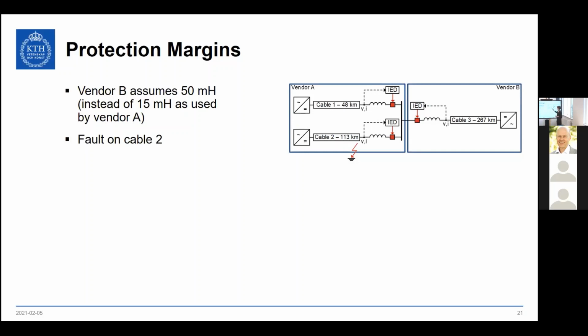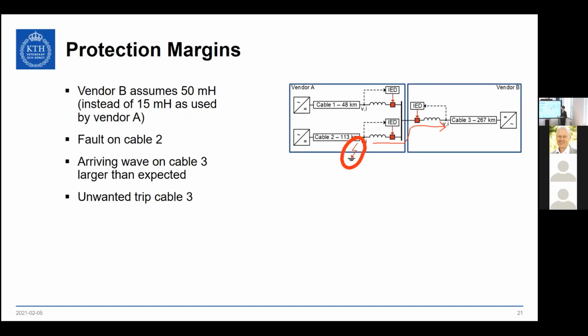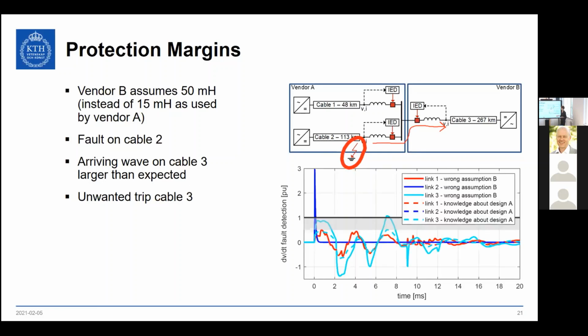And now I apply a fault in simulation here on cable 2, and a wave moves through this star connection to the measurement for the new vendor B's fault detection. The arriving wave is much larger than expected because the line inductor in reality is much smaller than vendor B thought, which results in an unwanted trip on cable 3, which basically means that Shetland is disconnected, although it was not necessary.